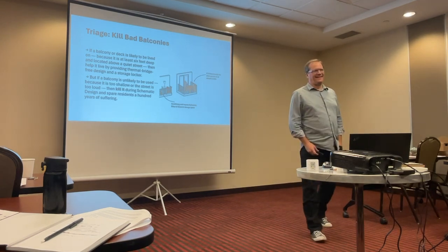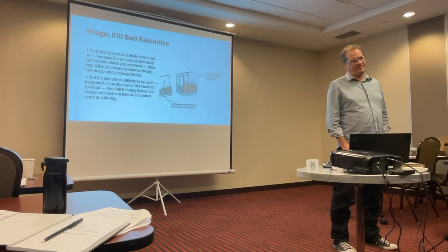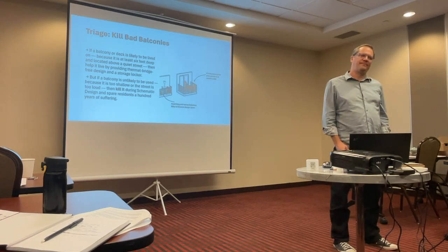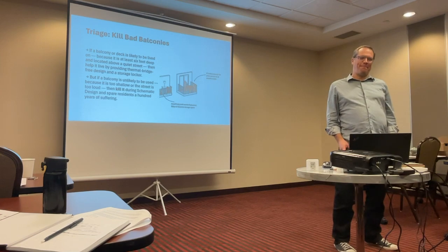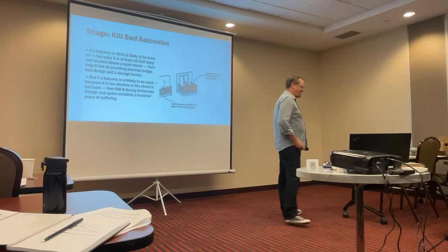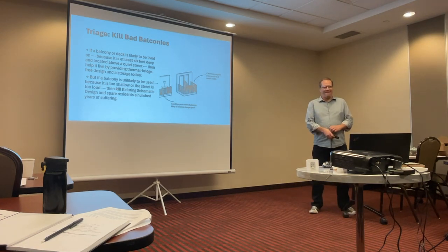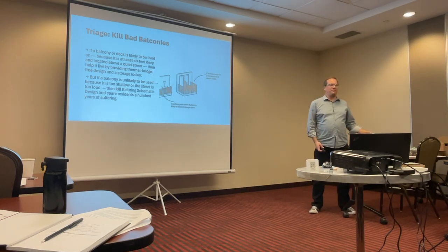Just to set, work on a larger building, and when we did an analysis of switching to a simple air conditioning system that required a short run to a one-to-one air conditioning system, it was less expensive to put a balcony and drop the condensers on the balcony than it was to go to a central VRF system with all that was involved. That's great. And we're going to talk about mini split service VRFs if we get there, but absolutely right. You need that balcony and you could pay for it right there.